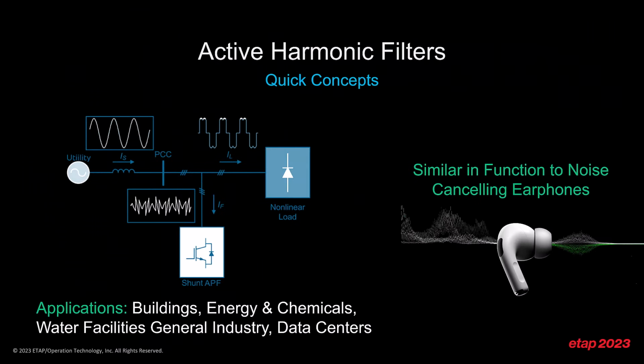Electrical networks with poor power quality usually result in financial loss. There's environmental impact, and of course there's safety concern. And it's all stemming from the fact that harmonics produce excess energy, heat, and that excess energy or heat results in excessive costs for operation of the electrical system. And it leads, amongst others, to frequent failures of equipment, reduced lifetime of the equipment, production losses, which of course indirectly can also affect the safety level of the installation.